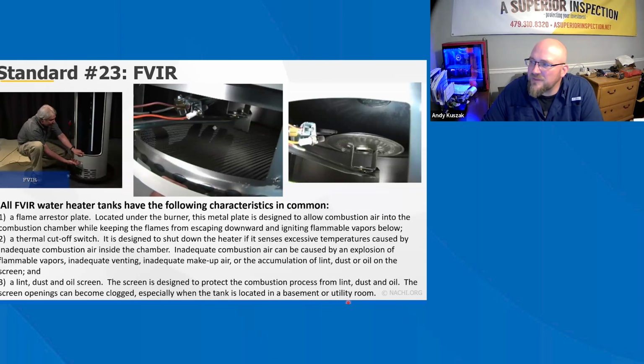If the tank is in compliance with the FVIR standard, it does not have to be raised 18 inches in garages or similar locations unless required by the manufacturer or local code authorities. An FVIR water heater has the following components: a device to prevent ignited vapors from passing out of the combustion chamber, a one-way intake system to control the movement of makeup air into the combustion chamber, and an inner door and burner assembly to create a sealed junction with the combustion chamber, preventing combustion air and flammable vapors from entering the chamber through the front of the water heater.